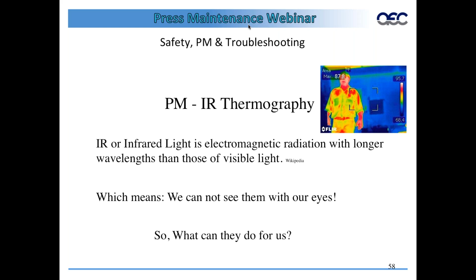Just to give you a few examples here. If you look at the panel on the left, here's a wire on top that no way with your eyes could you see that there's an issue of overheating. And I tell people, and I probably should do it when I get back home, to find somewhere to look at in your home, because this is the number one cause of home fires. This is probably where a bad connection is, and it's sitting there arcing all the time by not getting good contact, or it doesn't have a lot of surface area, and you don't have enough area there to conduct the amount of current that's passing through it. But when you take a quick look in a panel with a camera, you notice these things so quick that are issues or can be issues.